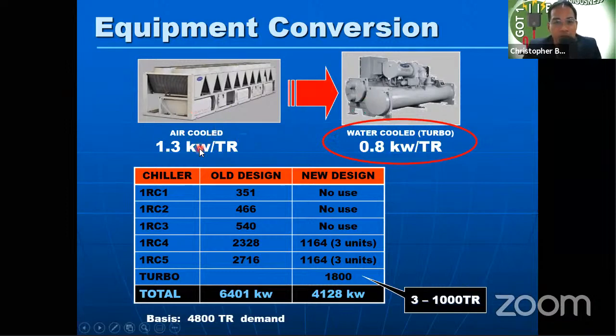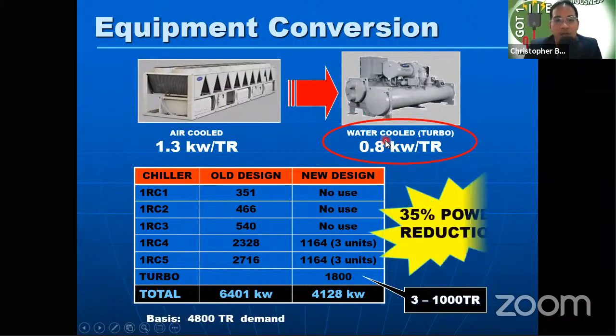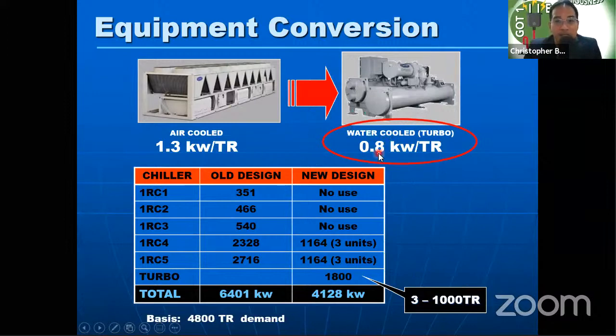So here, the air-cooled chiller has an energy performance of 1.3 kilowatt per TR. When we studied possible replacement, we ended up with what we call a turbo chiller, at 0.8 kilowatt per TR. You can really see the difference in energy performance right there.